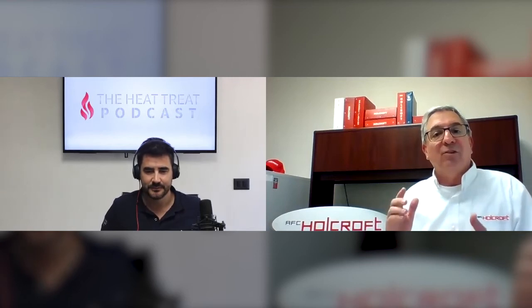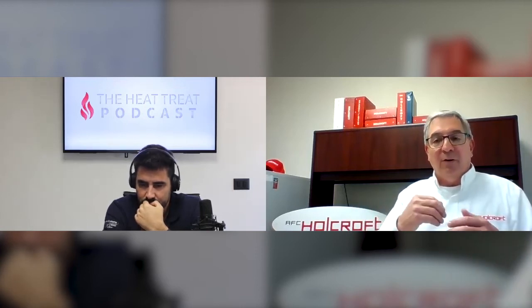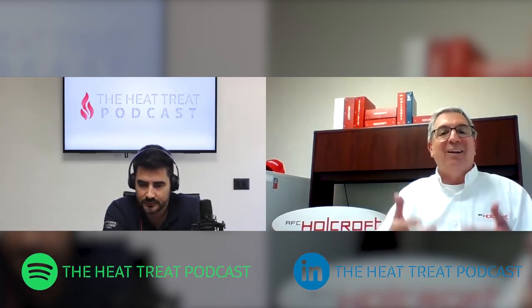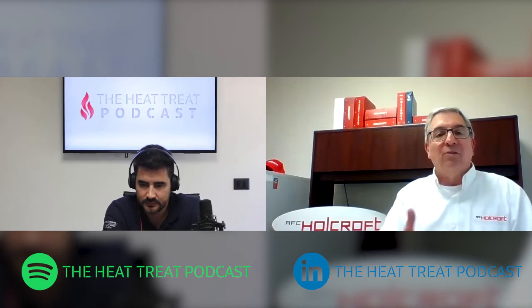So you want to keep things simple, and that's why in the early decades of my career, and even up to now, pusher furnaces were very reliable. They pushed large stacks of product through the length of a furnace repeatedly all the time. That's because all the mechanisms were outside of the heat and only in the heat for a very short period of time when you use them. So if you put mechanics inside of the heat, you have to deal with how reliable that is going to be over a life cycle.